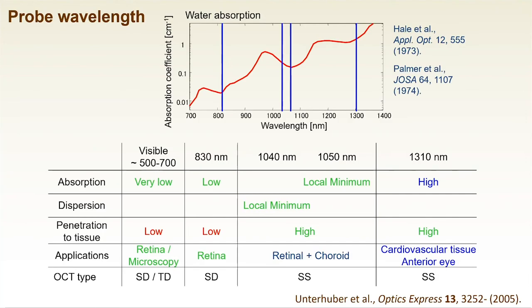Let's start with wavelength selection. The probe wavelength of OCT is normally in the near infrared, around 840 nanometers or 1.3 microns. How do you select the wavelength band? There is a certain strategy for this, and it mostly depends on the absorption of water, especially in the near infrared range.